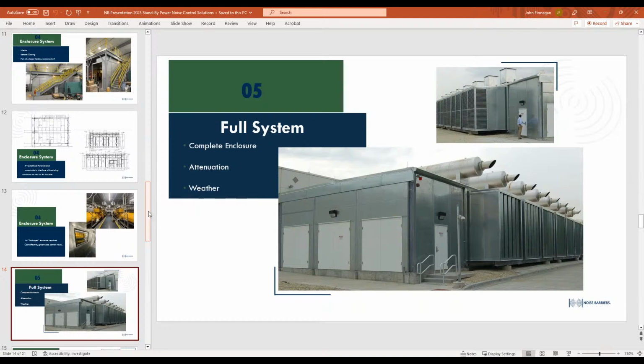In this case, you see a lot of double leaf doors for access into equipment in the switching rooms, and then a whole bank of exhaust mufflers and exhaust systems. This is a case where you're really banking half a dozen or a dozen gen sets into one big room. We do that, not that common because it's quite an expense, but the big data centers usually don't have one or two gen sets, they bank them. So there's economies here where you're doing one large room instead of a single room.